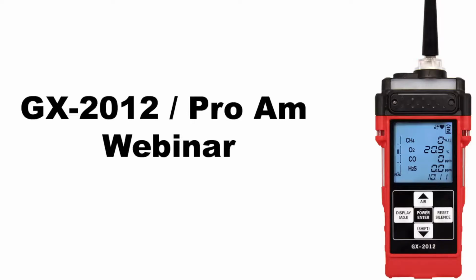Okay, great. Hey, Zach and Bob, are there any questions that you guys have specifically before we show you the GX-2012? We're going to show it to you in its normal operation as a 4-gas compliance tool. And then we're going to talk about the ability to put a 5th sensor in the unit, which allows us to auto range. I know this is a new term, but we're going to allow the instrument to move from a percent LEL measurement into a percent by volume measurement with your employees never having to touch the unit.